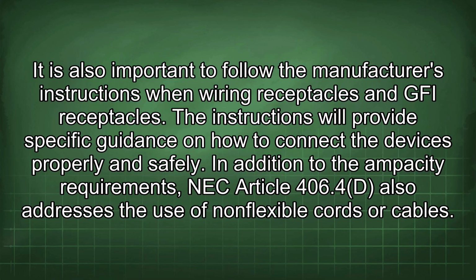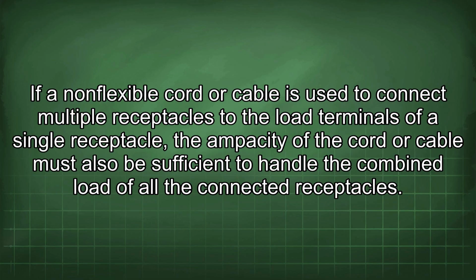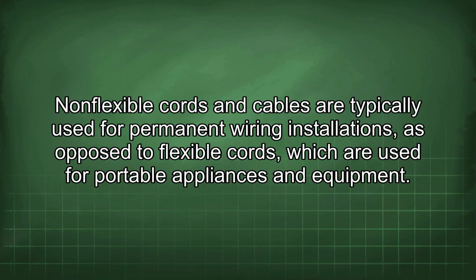In addition to the ampacity requirements, NEC Article 406.4d also addresses the use of non-flexible cords or cables. If a non-flexible cord or cable is used to connect multiple receptacles to the load terminals of a single receptacle, the ampacity of the cord or cable must also be sufficient to handle the combined load of all the connected receptacles. Non-flexible cords and cables are typically used for permanent wiring installations, as opposed to flexible cords, which are used for portable appliances and equipment.